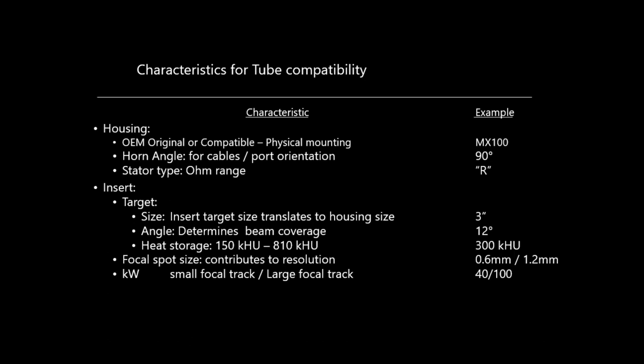You have the angle, which is one that determines beam coverage. Most common is 12 degrees. The heat storage in these rotating anode X-ray tubes, they're typically between 150 KHU, which stands for kilo heat units, and 810 KHU, kilo heat units. Talk about CT, we talk about heat storage in MHU, or million heat units, for the manufacturers of units.